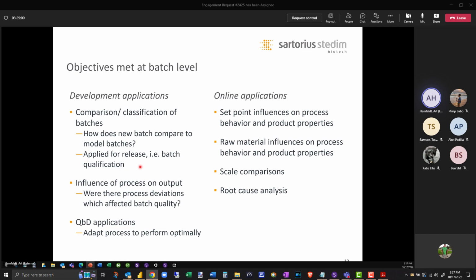So if I have this process running at plant A, I pick up the model and move it to plant B. You run, there are going to be offsets that have to be applied, but you run one batch, or we pull in one batch of data, we compare, apply those offsets, and now you have a model for the other plant, as long as it's the same process. Now, with that said, at that point you'd only pull in the process parameters, pH, temperature, things that are touching or sticking into the process. I wouldn't give a rat's banana about anything else. Only things that actually are measuring the material in the tank.